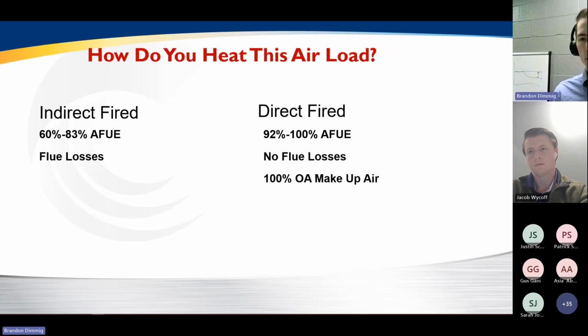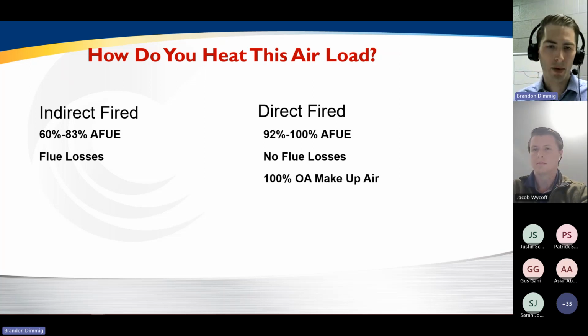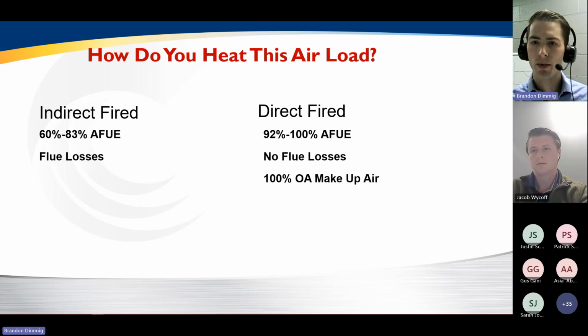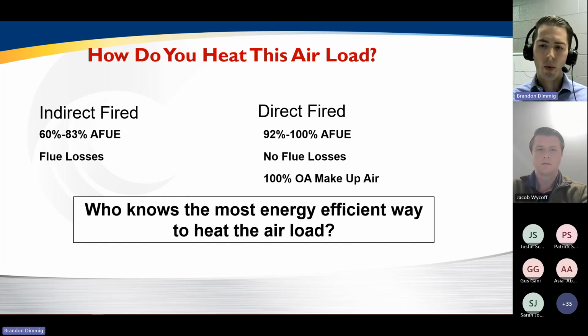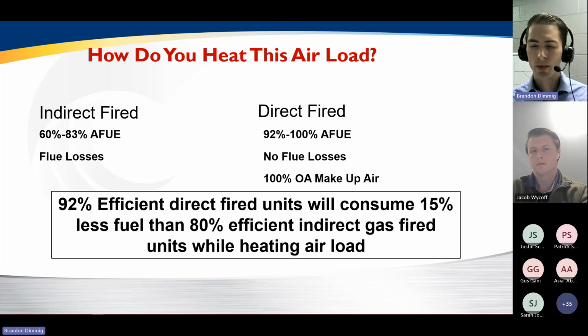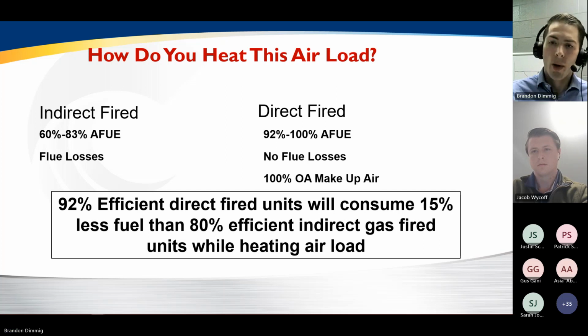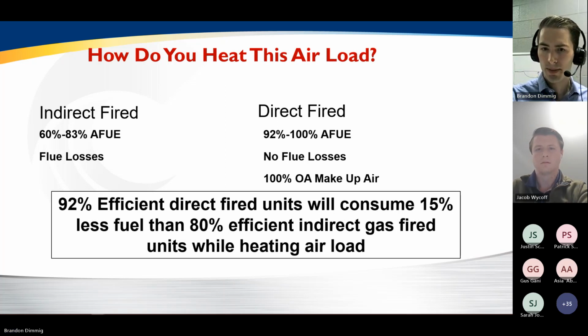There are 2 main systems that you can use to heat the air load of a building. One is a traditional indirect fired system. Could be unit heaters, could be others. And then direct fired, or HTHV. So let's look a little bit more at what this looks like. What's the more efficient way to heat the air load in the building? Direct fired is considerably more efficient, consuming about 15% less fuel than an 80% indirect gas-fired system, really because of the flue losses that an indirect fired system suffers from.